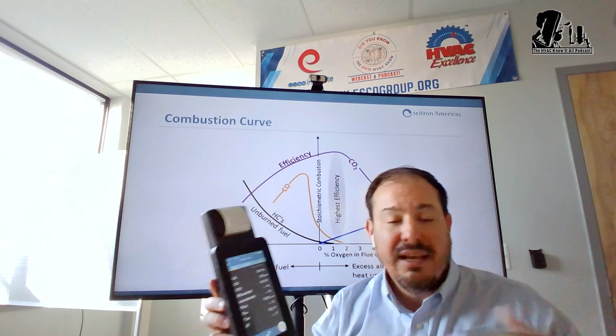It's a little bit about what we talked about last time, where now the technician in the field becomes the doctor. He has to take those readings and decipher what is good and what isn't. And sometimes what scares me, after teaching combustion for 20 odd years, is when I go in front of a room full of techs and say, okay, you're running a 90% boiler and you're doing an 80% furnace, where should your O2, your CO, your CO2, your draft, your temperature be? A lot of times, fairly enough, I get blank stares.